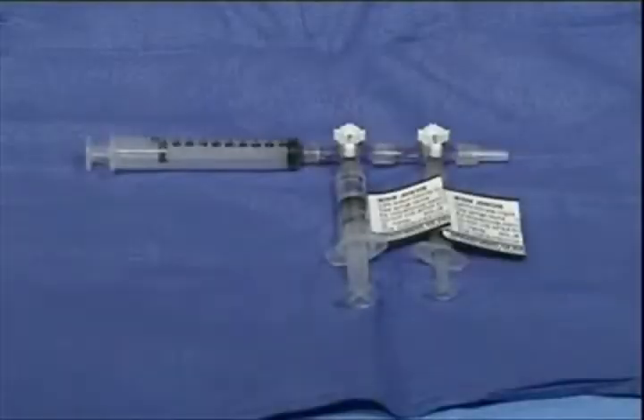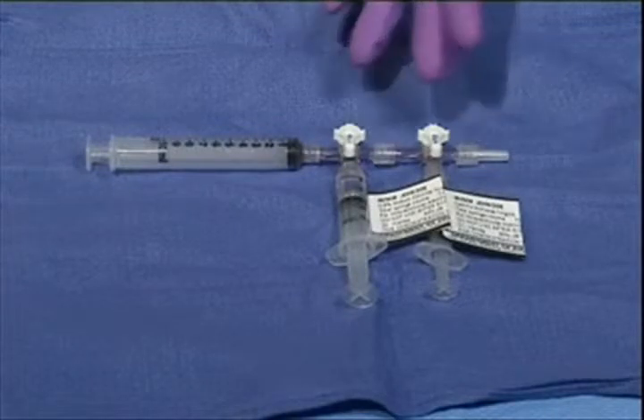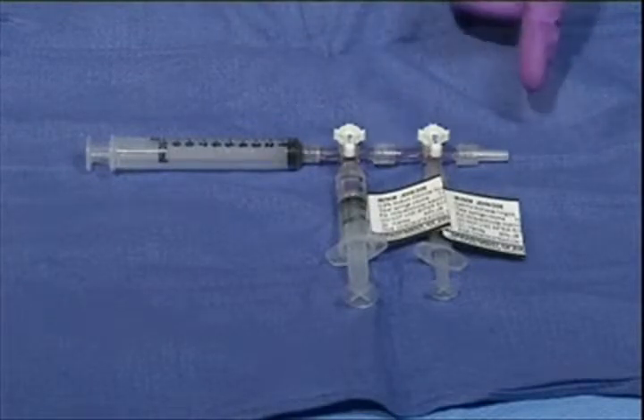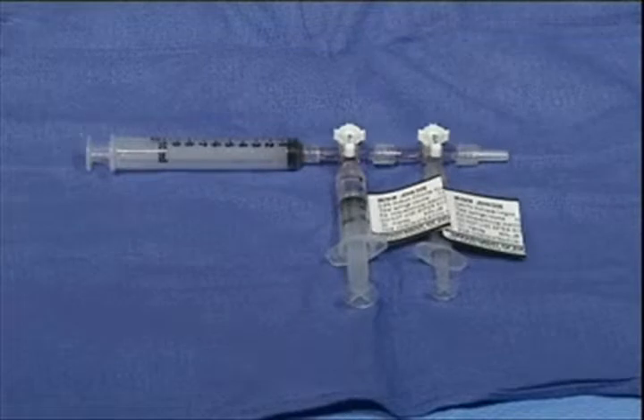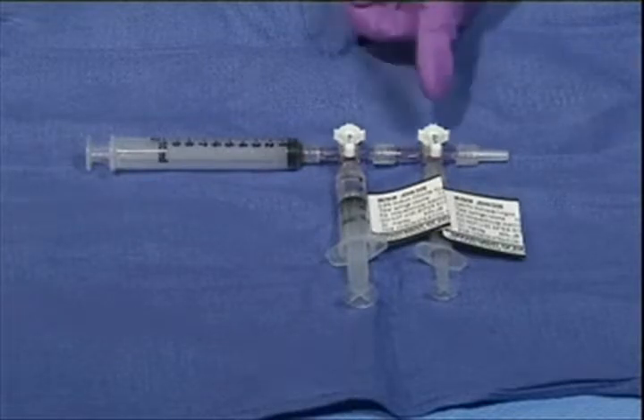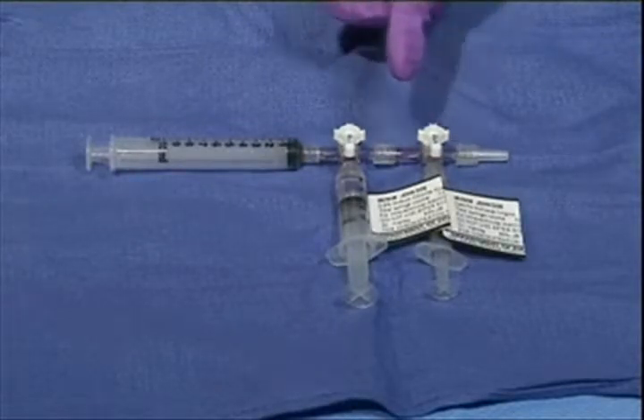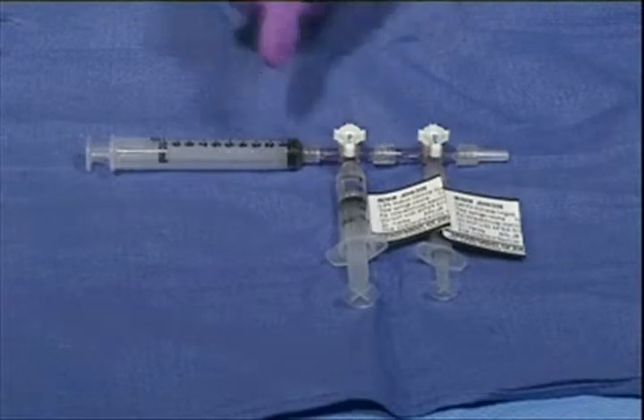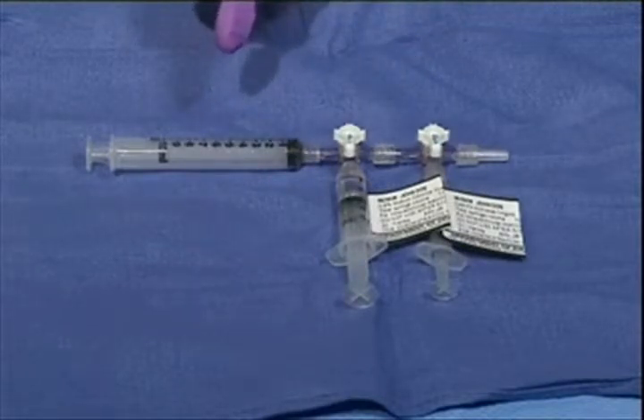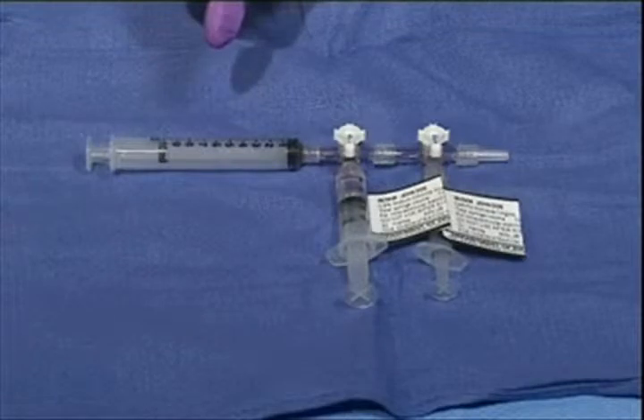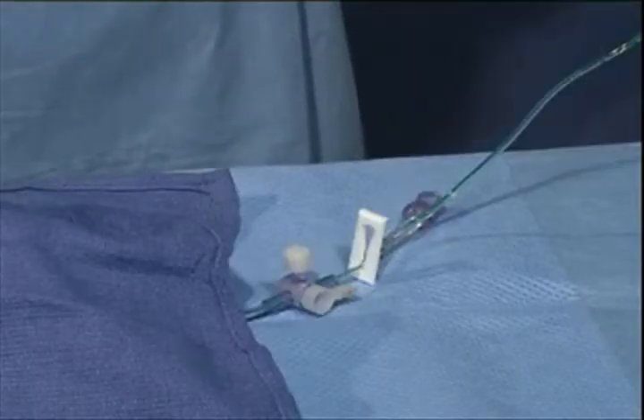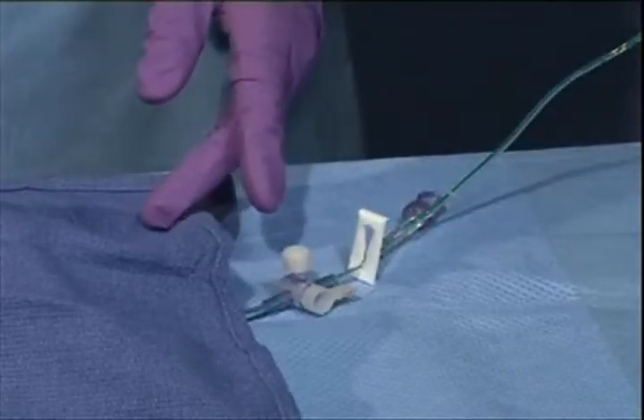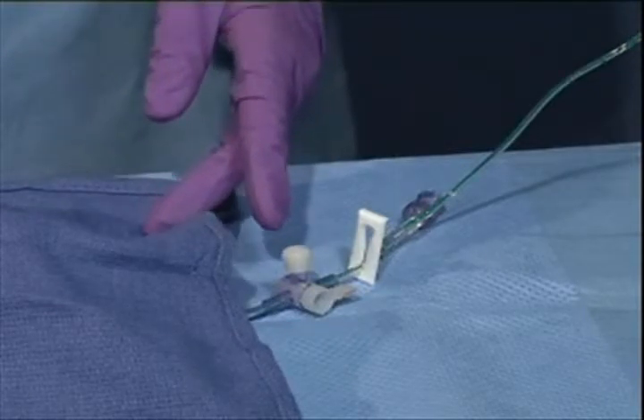This is the injection and aspiration apparatus. It consists of 3 syringes, 2 stopcocks, and 1 screw port on the end. The study drug is attached to the stopcock closest to the screw port. The flush is attached to the next stopcock, and an empty syringe for aspiration of spinal fluid is attached to the back stopcock. The apparatus screws directly into the port of the ventricular system closest to the head.